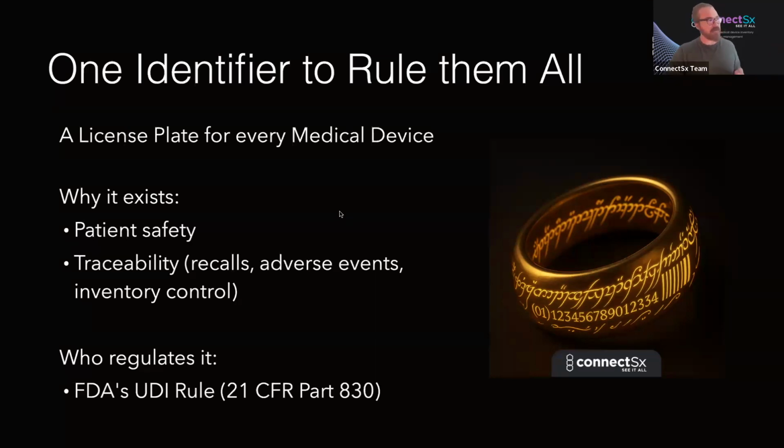And then who regulates it? Obviously, we're talking about the FDA here in the United States. And the final rule, I believe, was called 21 CFR Part 830, but they've published a number of guidances related to the UDI final rule, a lot of them in response to challenges that the industry faced and raised.